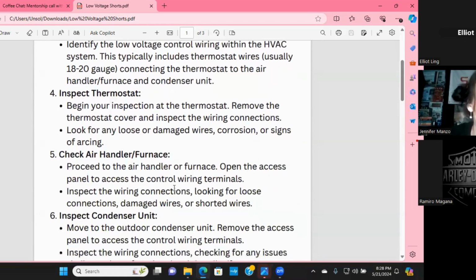And then inspect the thermostat. I don't actually agree with this. I put this in this position because it is probably what you should do. The thermostat can cause problems, but homeowners tend to think that it's the thermostat just as often as they think they're low on quote unquote Freon, right? So just because the customer calls you and says my thermostat's out, the problem is in the thermostat, you need to verify that because other things can short that thermostat. Definitely inspect the thermostat, but it doesn't have to be the first thing you do.